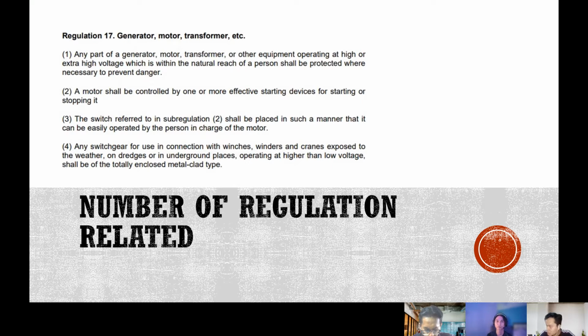Number one, any part of a generator, motor, transformer or other equipment operating at high or extra high voltage which is within the natural reach of a person shall be protected where necessary to prevent danger. Number two, a motor shall be controlled by one or more effective starting devices for starting or stopping it. Number three, the switch referred to in sub-regulation 2 shall be placed in such a manner that it can be easily operated by the person in charge of the motor. Number four, any switchgear for use in connection with winches, winders and cranes exposed to the weather on dredges or in underground places operating at higher than low voltage shall be of the totally enclosed metal-clad type.